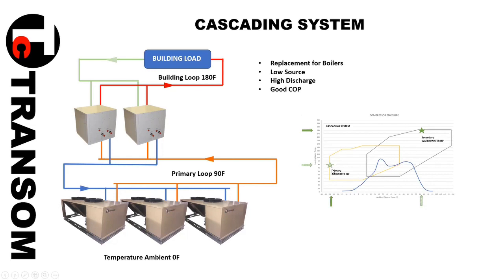So to get that first compressor sized up so that it matches the other one here, that would be it. Maybe now with more VFDs and so on that you can do with the compressors, that's in there. But I also noticed that the low source compressors typically are refrigeration type applications, freezers and whatnot. And typically they're on the refrigeration rack and they're just on-off compressors, so they're not built with variable capacities. You might be able to get down to maybe 15 degrees or something like that up here, and that's where you can do variable speed, but otherwise that's about it.